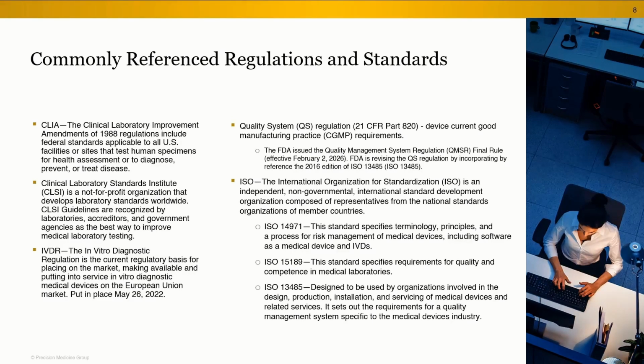Then we'll also talk a little bit about overall quality systems. So the quality system regulation in the US is 21 CFR Part 820. This quality system talks about good manufacturing practices, and of note, the FDA has issued a new rule regarding quality system where it's going to now be called the Quality Management System Regulation, which will be implemented in 2026. And this new rule kind of merges the 21 CFR Part 820 with ISO 13485, which is an international standard that organizations use regarding the design, production and development of manufacturing of medical devices.